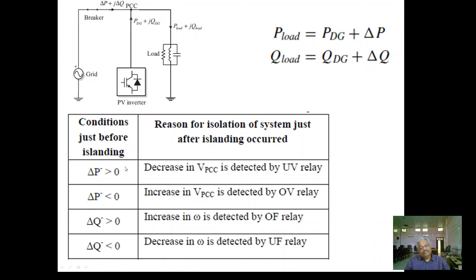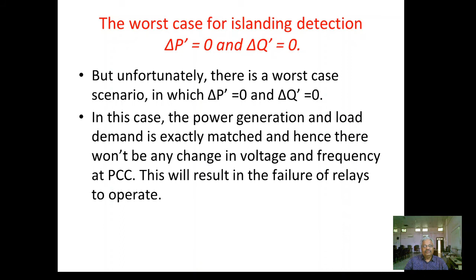What this means is the grid was not taking power from the distributed generation, or the distributed generation was not feeding power to the grid. In this case, the power generation and load demand are exactly matched. And whether the circuit breaker is opened or closed, there will be no change in delta P, delta P dash, delta Q and delta Q dash. Your over voltage, under voltage, over frequency, under frequency relays will be of no use because they are unaware of what happened upstream.